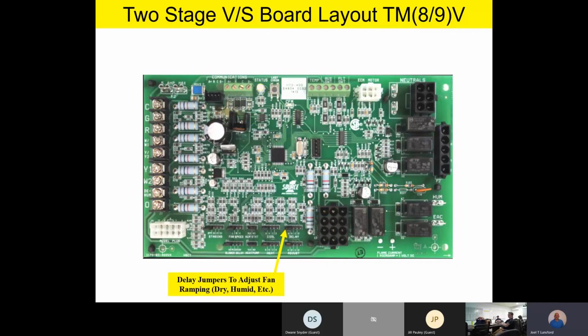Now, here's why we do that. Remember, team, whenever you have a really cold evaporator coil in the cooling mode, you're going to start pulling a lot of moisture out of the air going across that coil. And so that's the control scheme. We want to dehumidify quickly at the beginning of the cooling call, and then once the cooling call is over, we ramp that fan down again to 50% airflow, again to have really cool air off the coil, and then we shut it off. So that's just one example of the delay profiles that you can select.